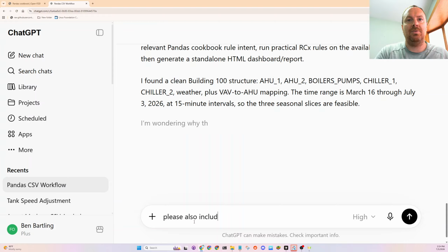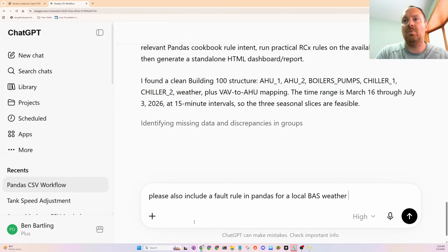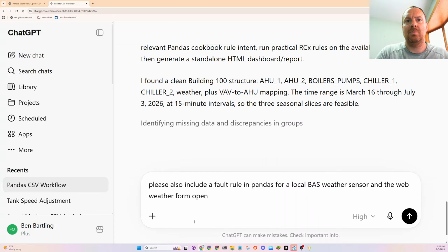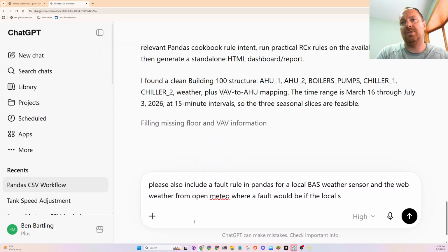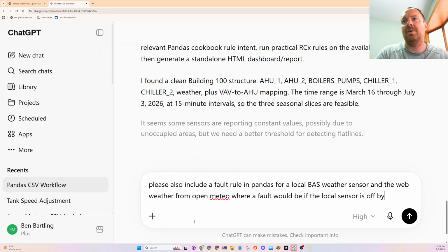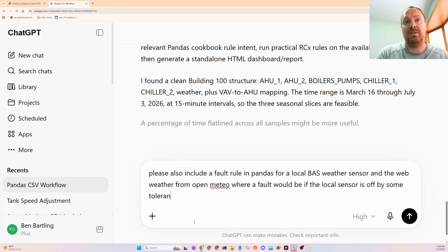Please also include a fault rule in pandas for a local BAS weather sensor versus web weather from Open-Meteo, where a fault would be if the local sensor is off by some tolerance, perhaps 3 to 5 degrees F.